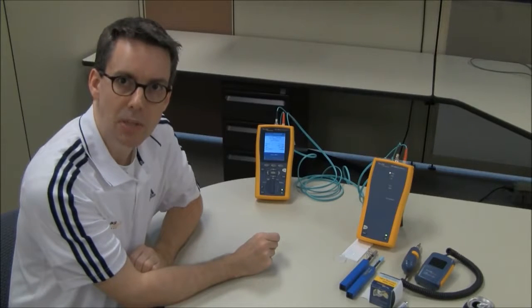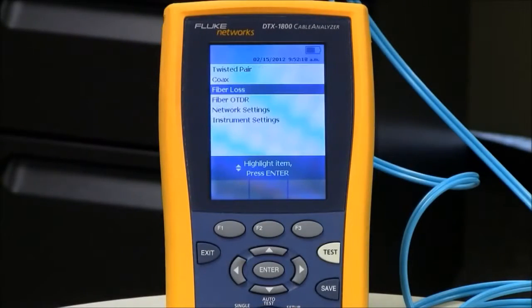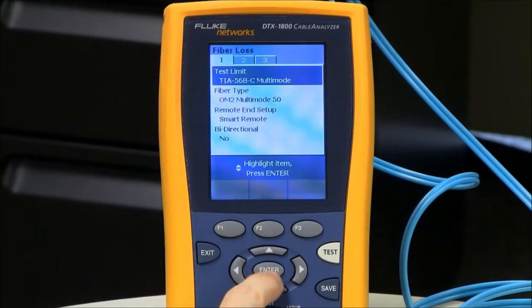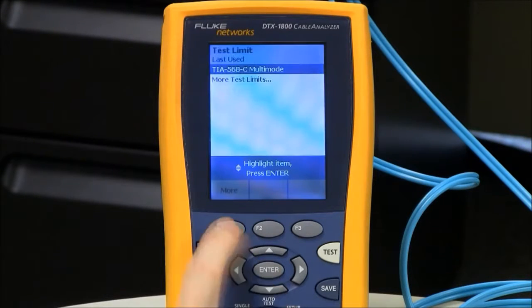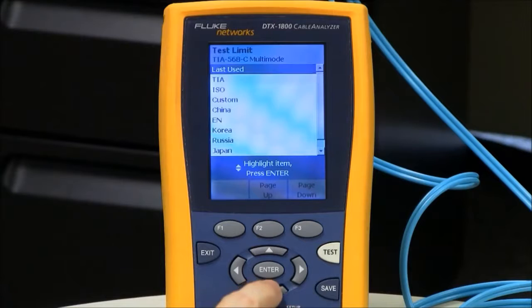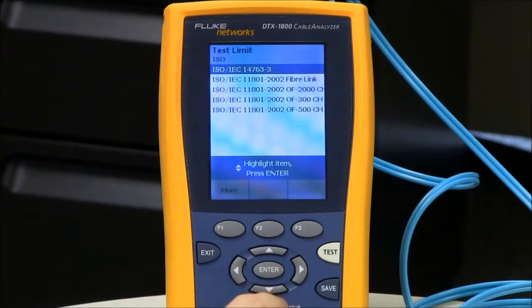Let's talk about setting up the DTX cable analyzer. I'm going to rotate the dial to setup, and with fiber loss highlighted, I'm going to hit the enter key. My test limit is currently set to TIA. If I wanted to change that to ISO, I would hit the enter key, F1 more, and go down to ISO, where I see the 14763-3 standard.